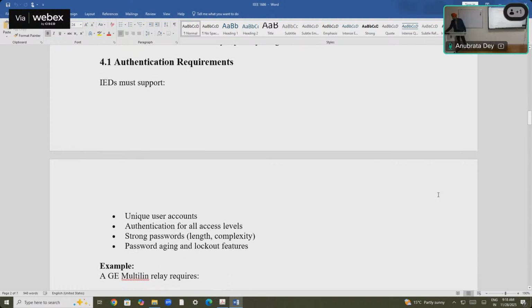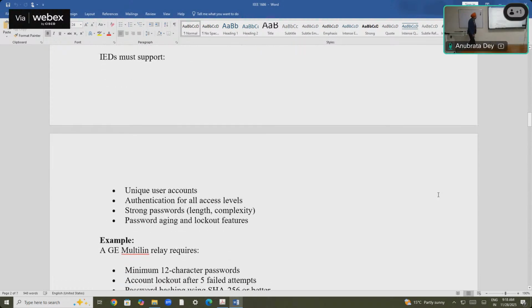What are the authentication requirements? Some of these are common sense: unique user accounts, so it shouldn't be a common username and password for 15 people - I don't know if that happens in your facility or not. Authentication is required for all access levels, it doesn't matter if it's an observer, there has to be authentication. And strong passwords, both in terms of length and complexity, plus password aging and lockout features - if you try 3 times, it should lock you out, for example.